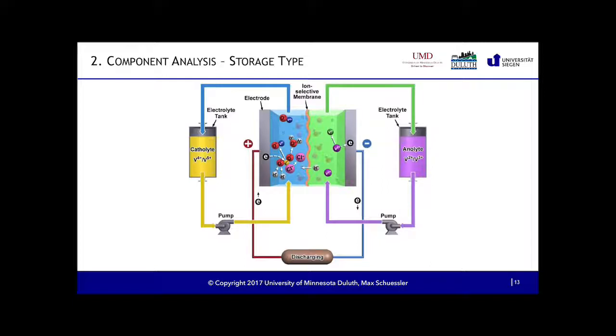In the case of the vanadium flow battery, the electrolyte that is used is of course vanadium, but at two different charges. Which means if I pump it through the cell, it will get rid of one electron which tries to get through a metal conductor somehow, and the ions will go through a membrane into the other electrolyte. And they can recombine here, and since I can pump this electrolyte in this circle and can pump this electrolyte in this circle, depending on the size of my energy storages or my electrolyte storages, I can scale the energy supply of my battery just as I want it to be.